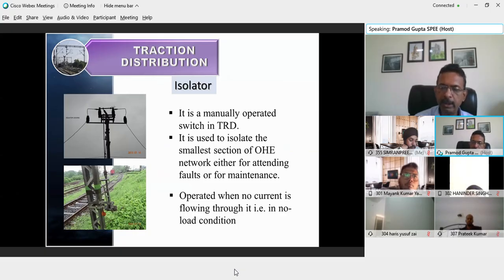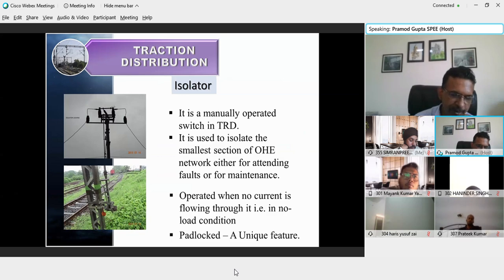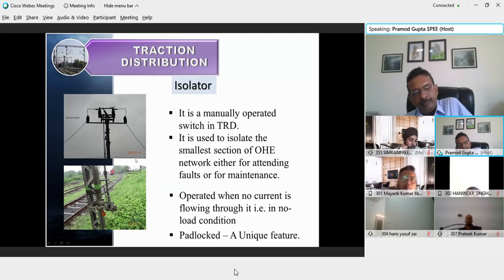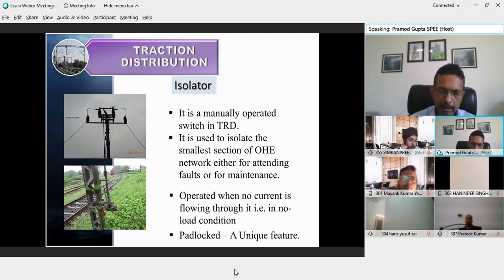We have to ensure that no current is flowing through it. There is a concept of padlock, a unique feature provided on Indian Railway to ensure safety of the manpower. Whenever we want to isolate the power supply, there is a lever provided at the foot of the mast on which the entire isolating assembly is mounted. The maintenance staff can operate this lever, and when it gets rotated by 180 degrees, the isolator opens and the circuit gets isolated.